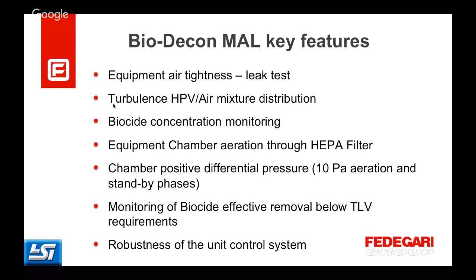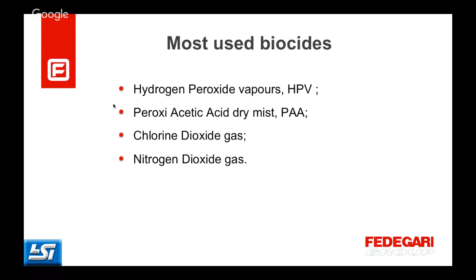Also, we have chamber aeration, and this will happen through a HEPA filter, and we need to guarantee a chamber positive differential pressure during the standby or idle phases. We need to monitor the biocide effective removal, which must be below the threshold limit value requirements, and everything has to be handled through a very robust control system. So the most used biocides, as I told you, are hydrogen peroxide vapor, peroxyacetic acid dry mist, chlorine dioxide, and nitrogen dioxide gas.